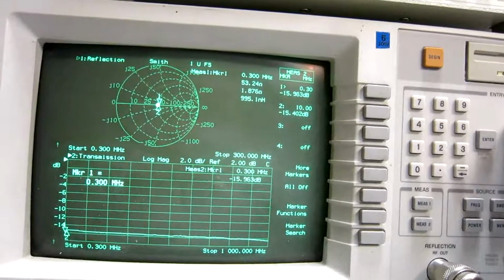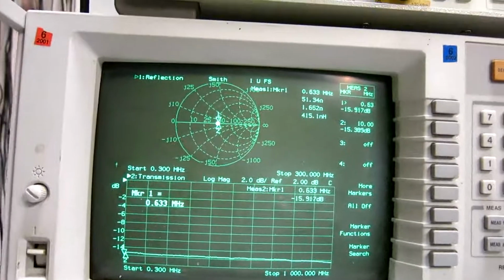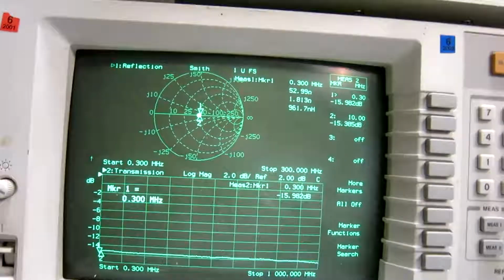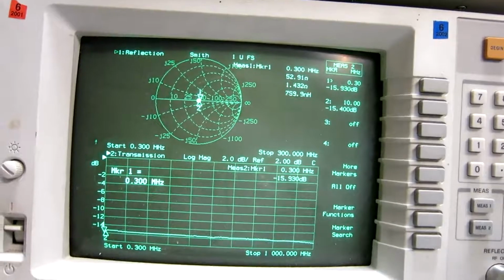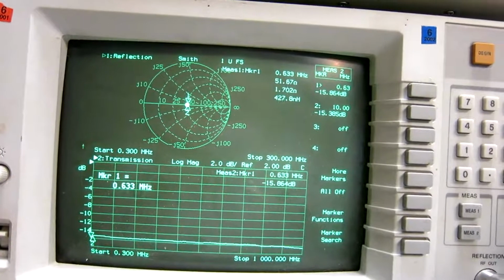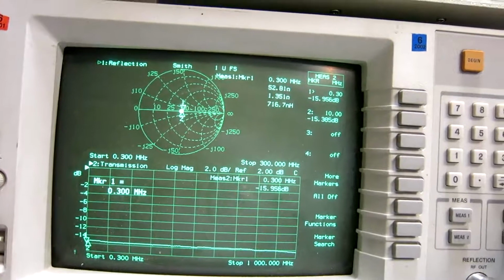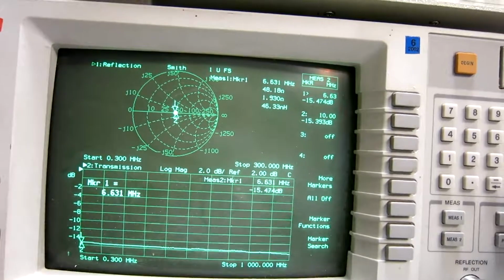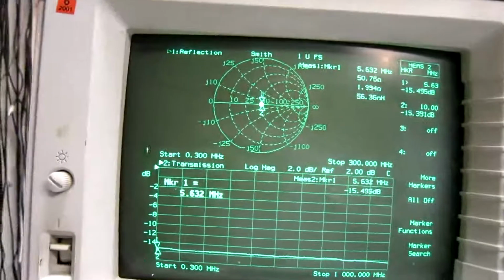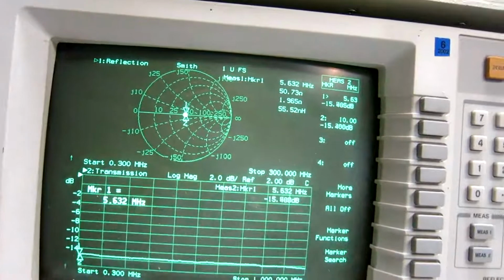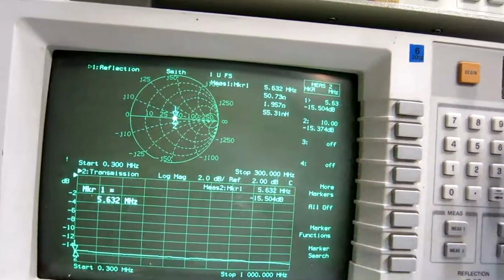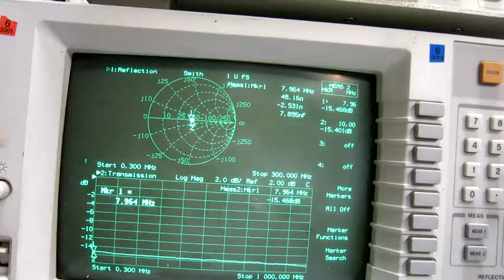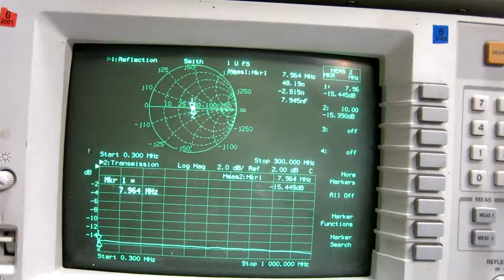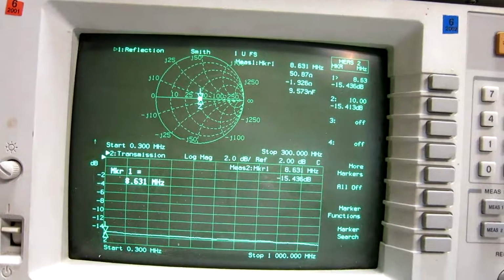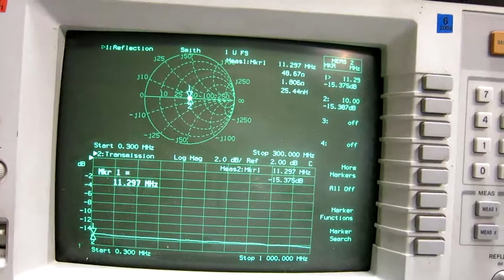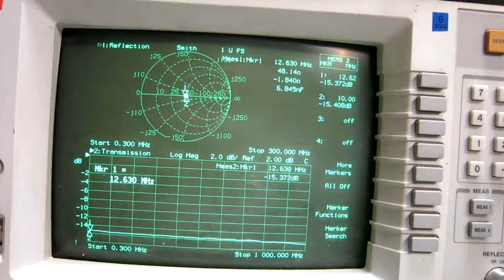The lowest frequency I can get is 0.3 megahertz, and there the attenuation is higher. I don't know why, but it's 15.9. So in the evaluation, you can see at 5 megahertz it's 15.5. But I'm going to test this unit at 14 megahertz, and 15.3 is fairly accurate.